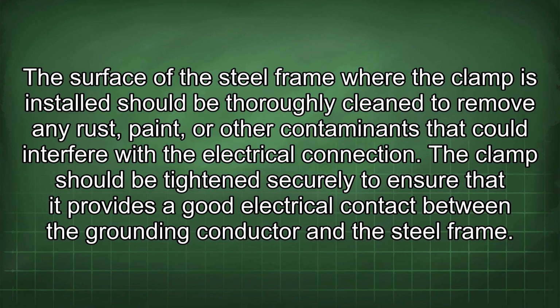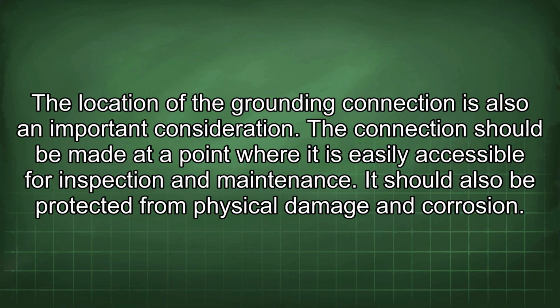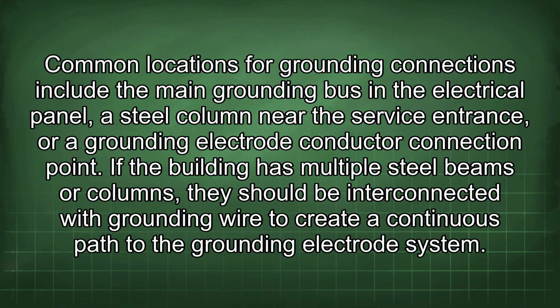The clamp should be tightened securely to ensure that it provides a good electrical contact between the grounding conductor and the steel frame. The location of the grounding connection is also an important consideration. The connection should be made at a point where it is easily accessible for inspection and maintenance. It should also be protected from physical damage and corrosion. Common locations for grounding connections include the main grounding bus in the electrical panel, a steel column near the service entrance, or a grounding electrode conductor connection point.